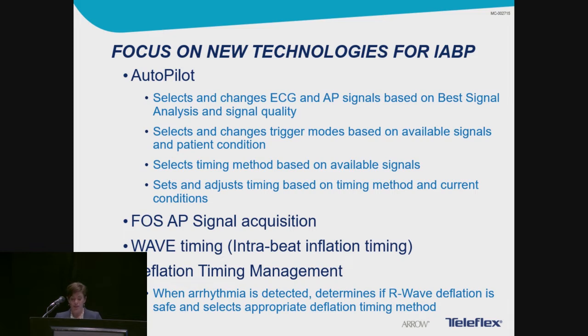Now, the next technology to review is our fiber optic arterial pressure waveform signal acquisition. It provides a real-time, high-fidelity AP signal. Now, this activates our wave inflation timing algorithm, which can increase the support from the balloon pump anywhere from 60 to 90 minutes per day. Next, wave timing uses our Windkessel model to convert aortic pressure to flow, and the inflation is set at a specified point on the flow wave, which is synchronized to aortic valve closure.